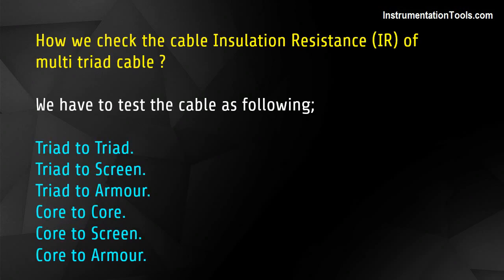How do we check the cable insulation resistance (IR) of a multi-triad cable? We have to test the cable as follows: triad to triad, triad to screen, triad to armor, core to core, core to screen, and core to armor.